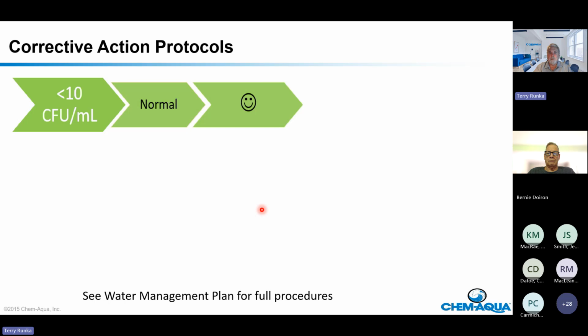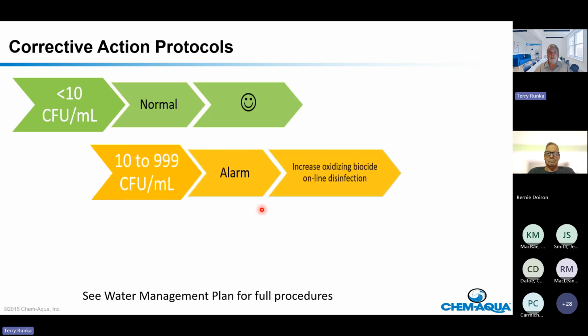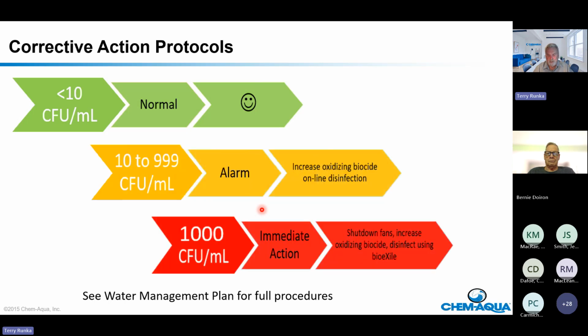Now, what are those corrective actions? I'm not going to get into exactly, but less than 10 colony forming units is normal, and there's nothing that you technically have to do. I've yet to meet any hospital that gets 10 and doesn't want to do a disinfection, but that's okay. It's not mandated that you have to. At 10 to 999 colony forming units per milliliter of total Legionella pneumophila, immediately we want you to increase your biocides, and within a couple of days, we're going to be there to do a disinfection and try to kill it.